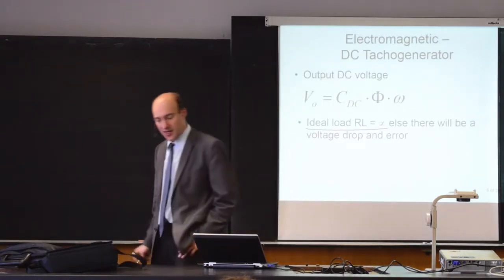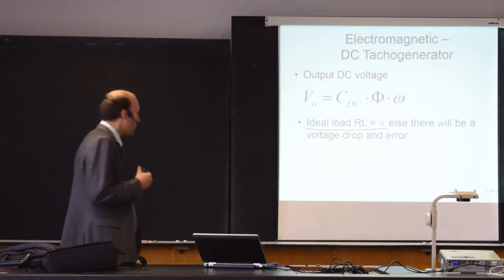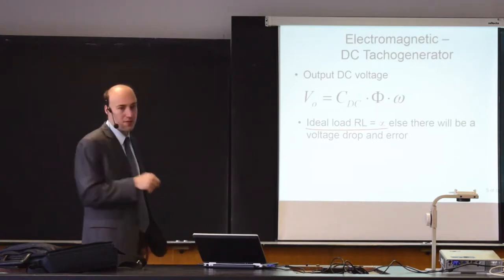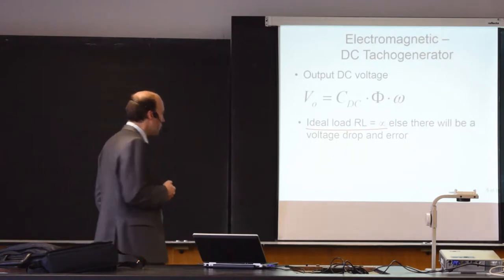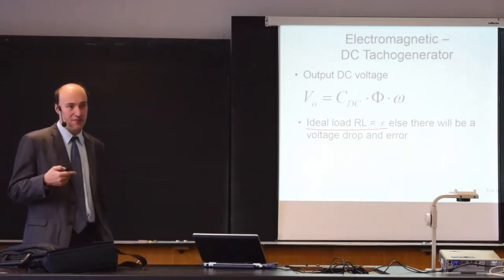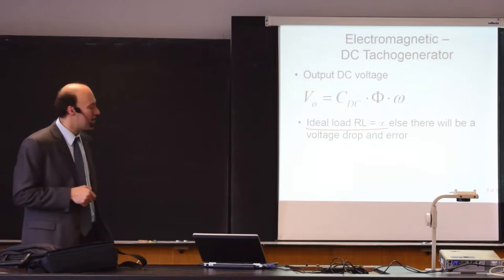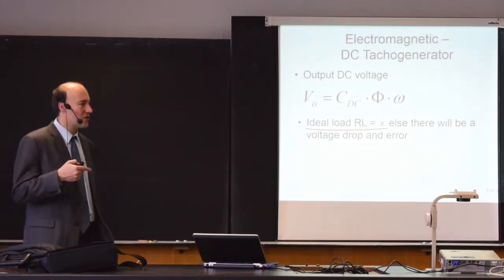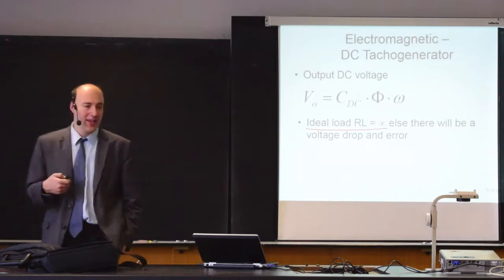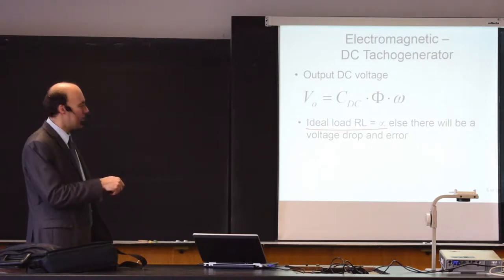The output voltage is a function of three things: it is a function of angular velocity — which is what we want to measure — it is a function of magnetic flux, where higher flux gives higher voltage, but this is given by the permanent magnet so it's a constant. The third value, C_DC, is also a constant describing the construction — it accounts for the size of the air gap and the materials used. So basically the output voltage is a linear function: a constant value times angular speed.